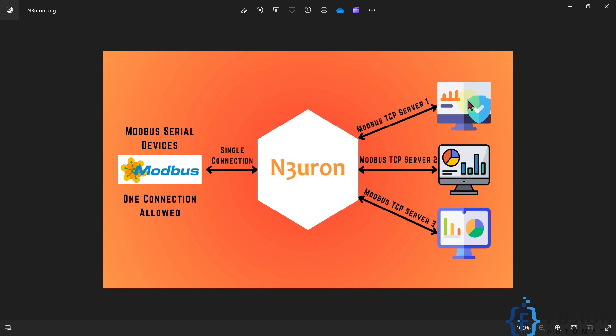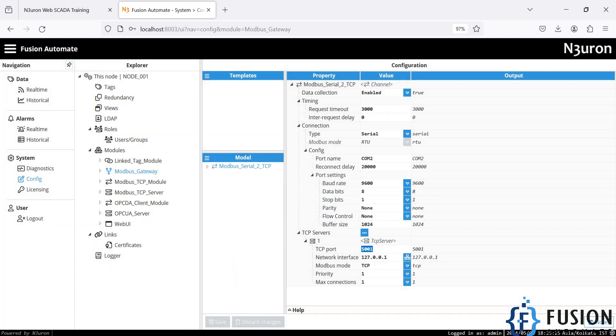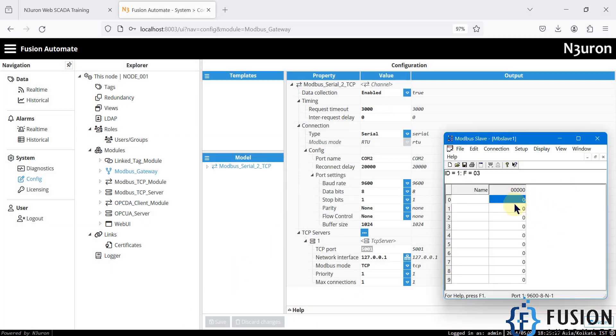When you create a Modbus TCP server inside the N3uron Modbus Gateway, it will only allow one TCP connection at a time. So if you want to provide data to another application, you have to create a second Modbus TCP server. For a third application, create yet another TCP server inside the Modbus Gateway. The first Modbus TCP server is now created and all data from this Modbus serial device will be available on Modbus TCP.